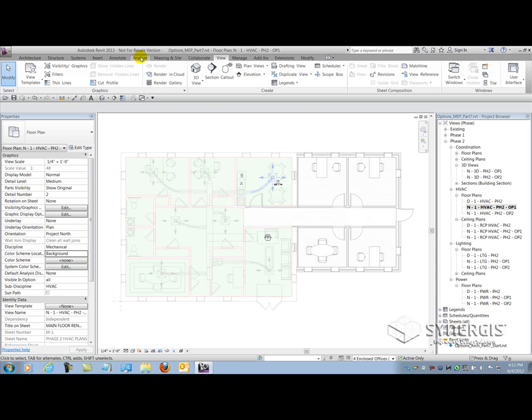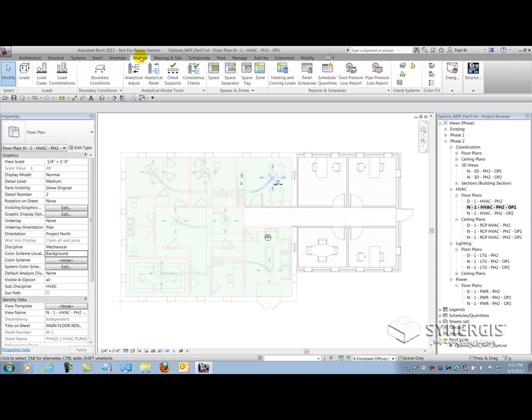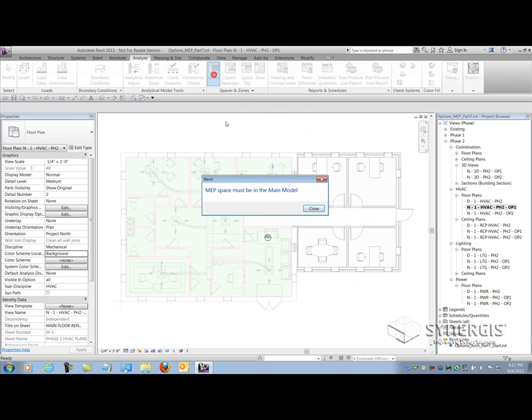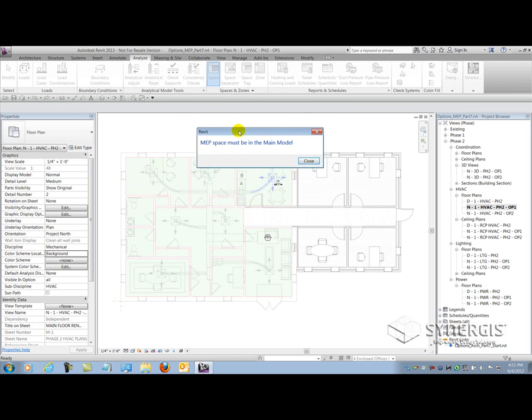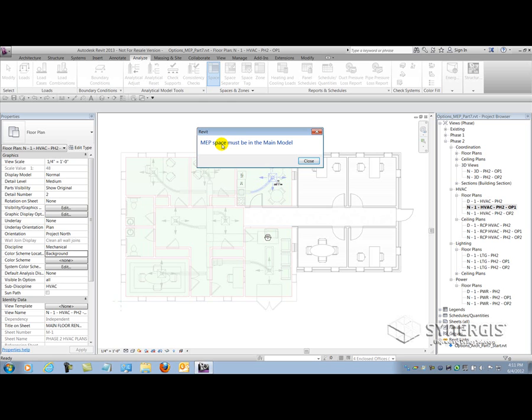If all goes to plan, spaces should go in just like rooms, correct? But when you get into the analyze tab and select your space tool, Revit will immediately prompt you to let you know that MEP spaces must appear in the main model. Here's the limitation when consulting with design options on the MEP side of things. You can only use spaces in the main model. Unfortunately, I will not be able to explore the different energy models for each option. The current workaround is to bind each of the options in the architects file and save them as separate linked files that you can bring into an MEP host file and then analyze each host file separately.